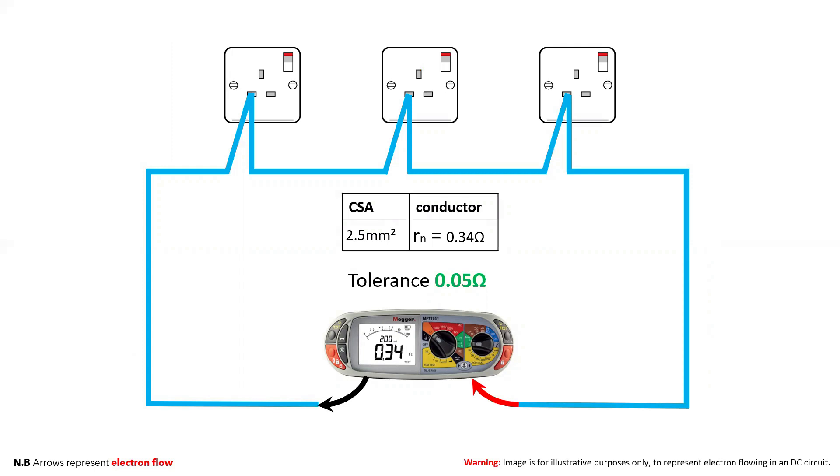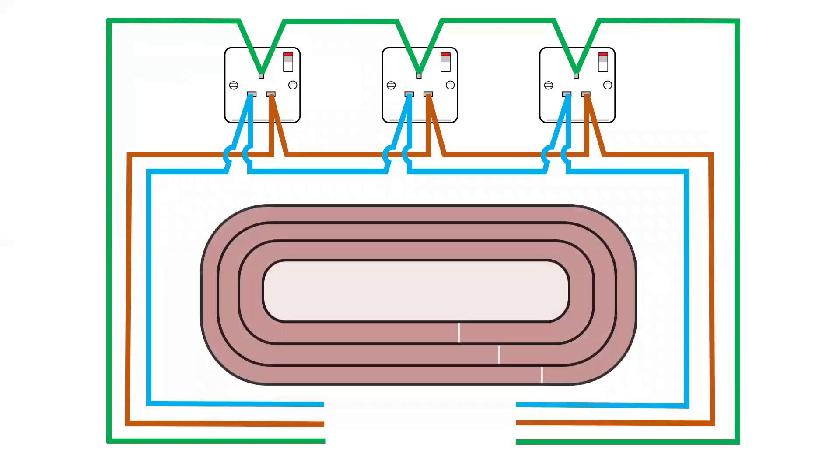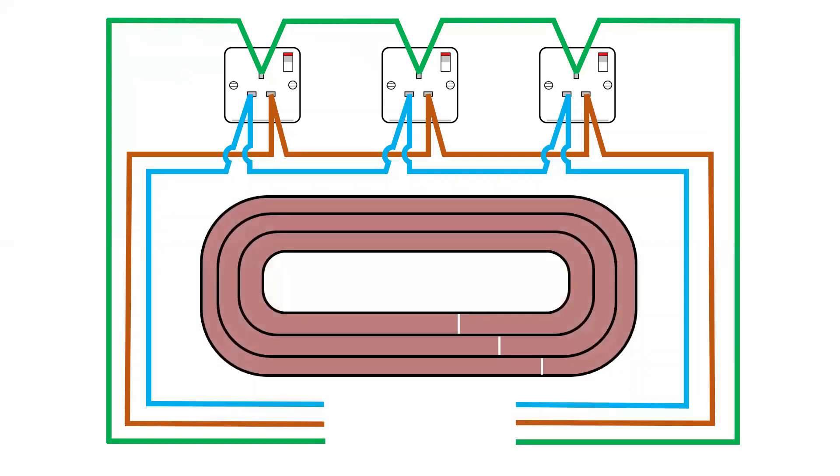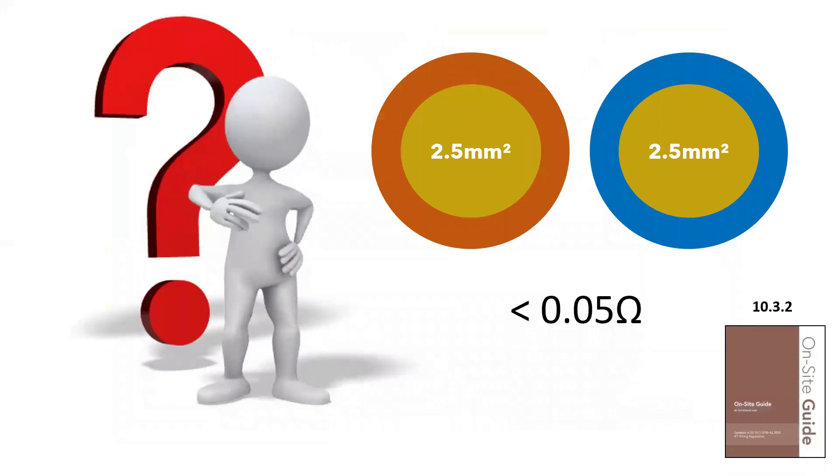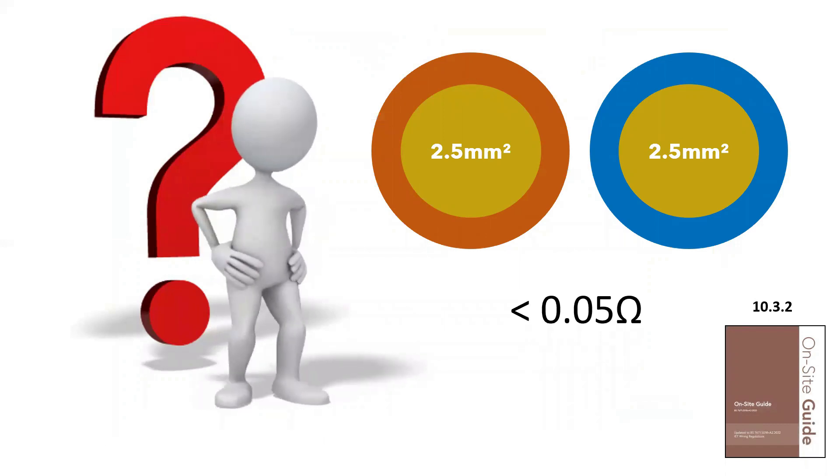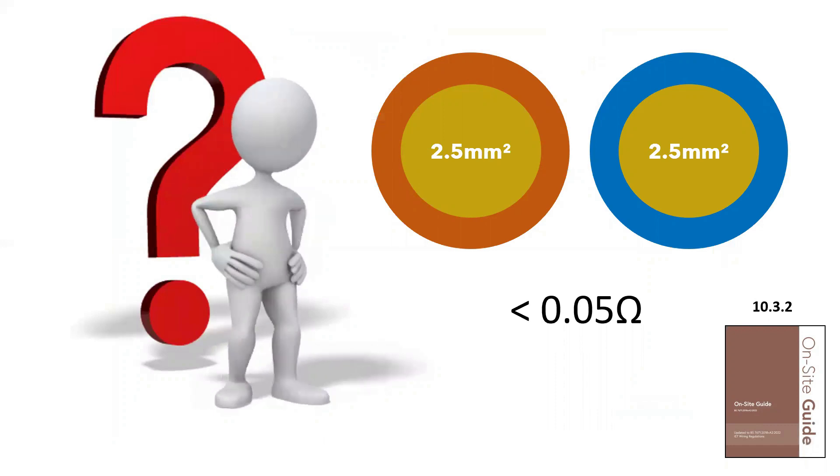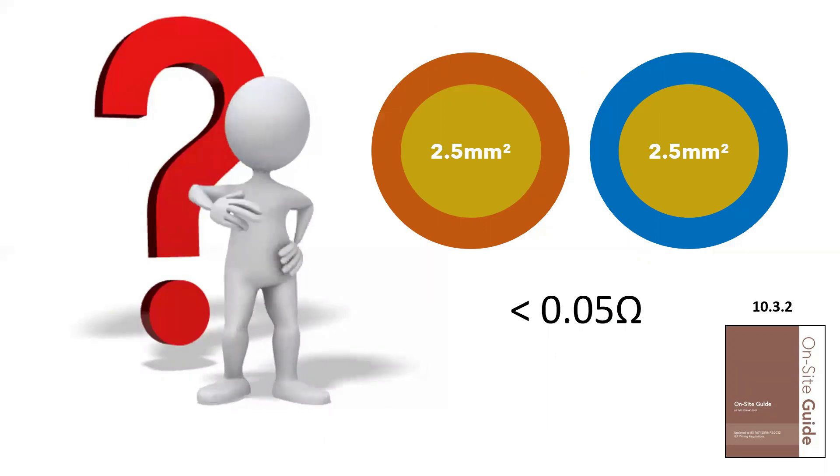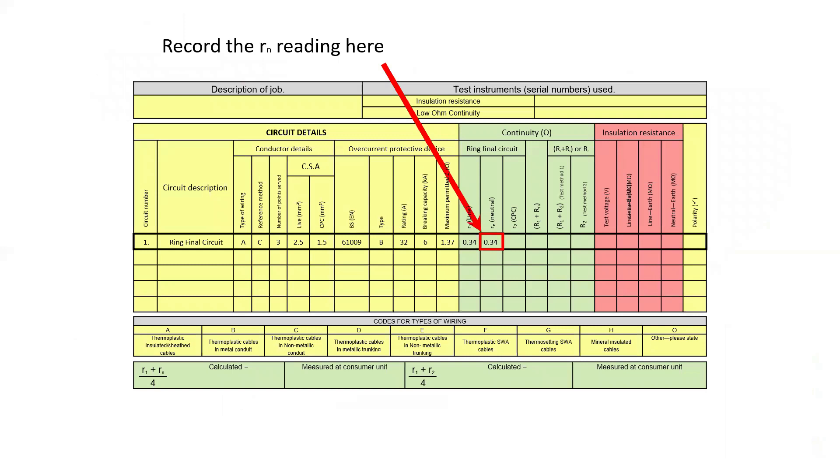We then repeat this process for the neutral conductor, also known as little rn, and because it's the same size length and CSA of the line conductor we are expecting almost the same result. Just like a runner on a track, the conductor on the inside of the bend will cover a slightly shorter distance. There is a tolerance value given in the on-site guide of 0.05 ohms. If the resistance measurement you are taking is not the same within the 0.05 ohm tolerance, then you need to begin fault finding. Once satisfied that our readings are correct we can record the reading of 0.34 in the neutral column marked rn.